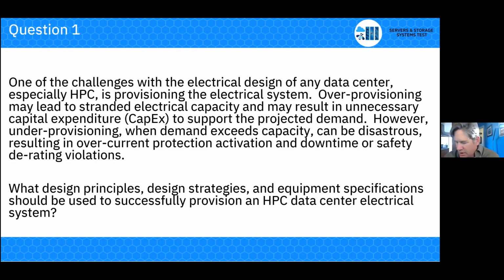Yeah, thanks, Joe and Brandon. At LANL, I'll give some perspective from the utility side. As our mission and HPC load grow, it taxes many of the external distribution and transmission systems we operate. One thing we've spent a lot of time on is thermal verification of the underground feeder circuits and combined duct banks, which turns out to be quite limiting if you're stacking too many circuits without the right thermal properties for your soil. If you have an HPC system that's going to run LINPACK or some other major stressor power demand event, doing that in a cold period has less thermal impact on those feeder circuits—they can tolerate more.